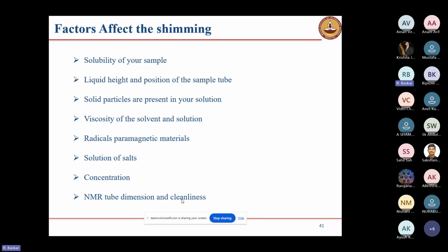Next one is the relaxation delay. We have to give the proper relaxation delay. For example, if your compound is paramagnetic, the relaxation will be very fast. At that time we have to give a shorter delay. Some of the compounds have a longer relaxation, so at that time we have to give a proper delay time. Otherwise, it will not relax completely and we won't get the NMR signal. So that's why the D1 is also most important. Next one is the number of scans. If your sample concentration is too low, we have to give more number of scans. That also we have to set.